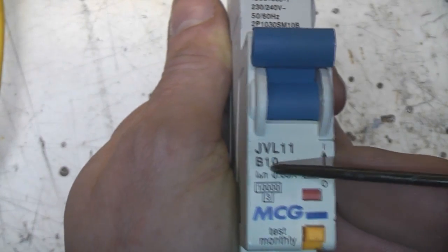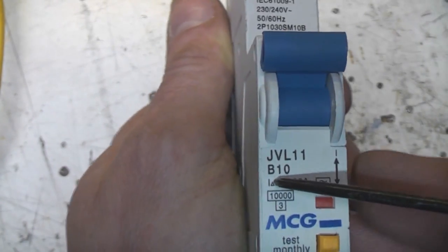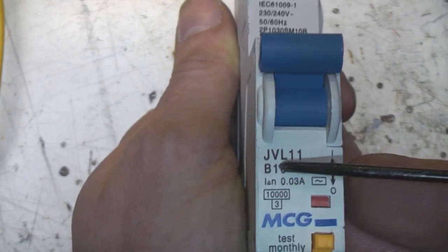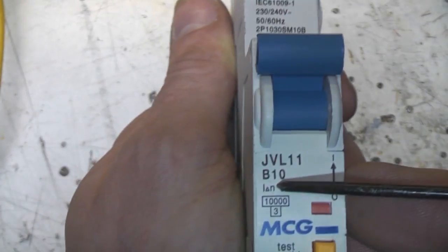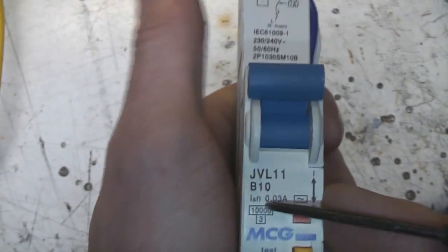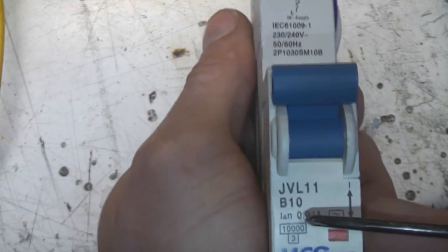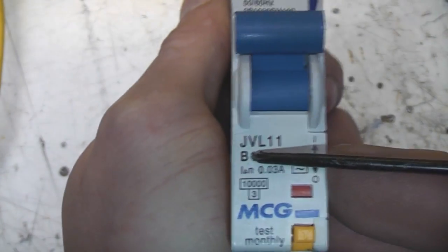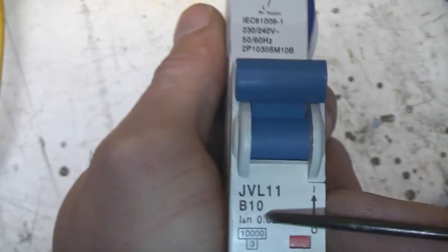So a B is a fairly standard one that you use on normal wiring. The higher letters come in C and D, and it's basically about surge capability. If, for example, you've got a large motor load or a large number of switch mode power supplies with a high inrush current, you tend to use a higher rated breaker on those so that their switch-on surge won't accidentally trip the overcurrent protection.